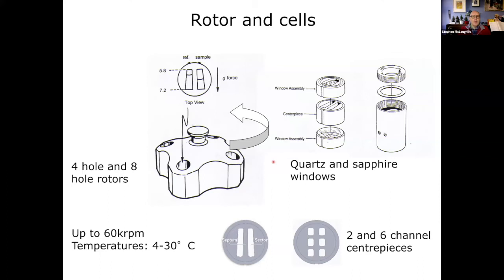For the setup, we need special rotors that have holes in them so you can look through them. They hold cells into which you clamp an assembly with a centerpiece that holds the sample, clamped between two windows. You can get different types of centerpieces — a two-sector or six-sector centerpiece, plus a variety of other specialized ones.